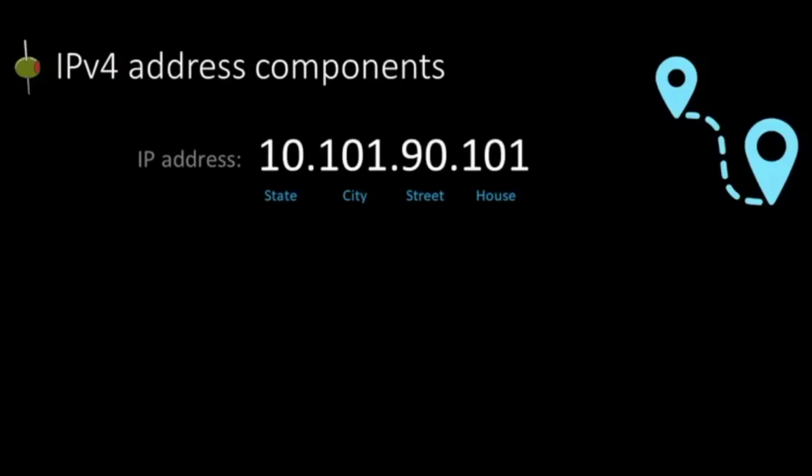So if you have multiple nodes that come on with the same IP address, it's called an IP conflict. And many systems, many switches will just stop communications with both of those devices. And oftentimes you have to rectify that and then restart those devices to get them to come back onto the system. So if you have a device that's not communicating, maybe look for an IP conflict and see if that's an issue.